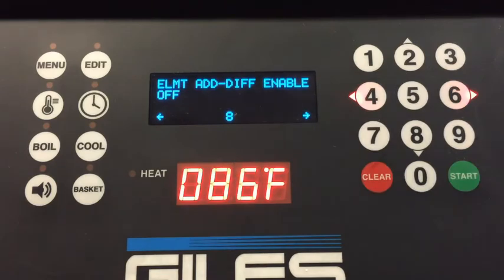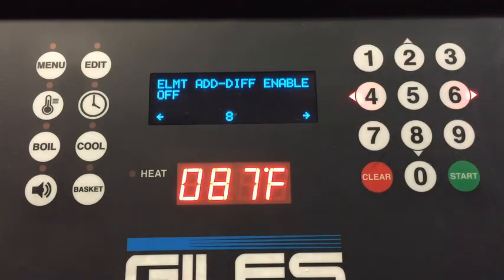Element add level, add diff enable. That is, if you have the fourth probe, you would have this turned on. This particular unit, this controller, is on an older unit that does not have that probe, but that's all. It just enables the controller to look at that fourth probe.